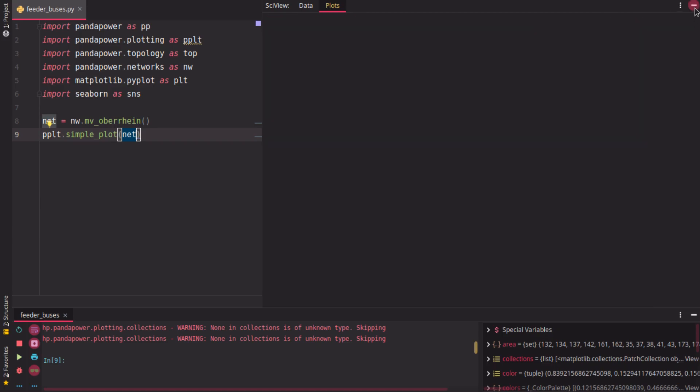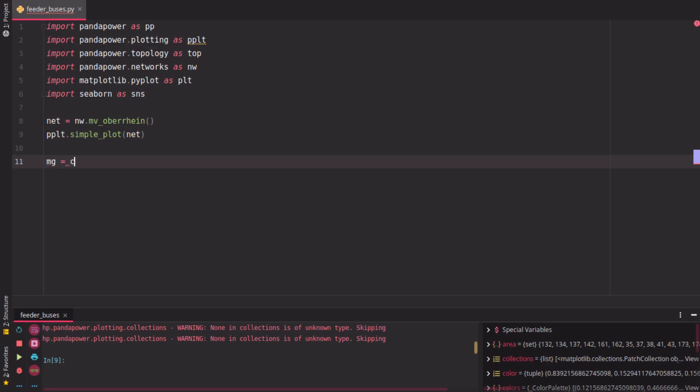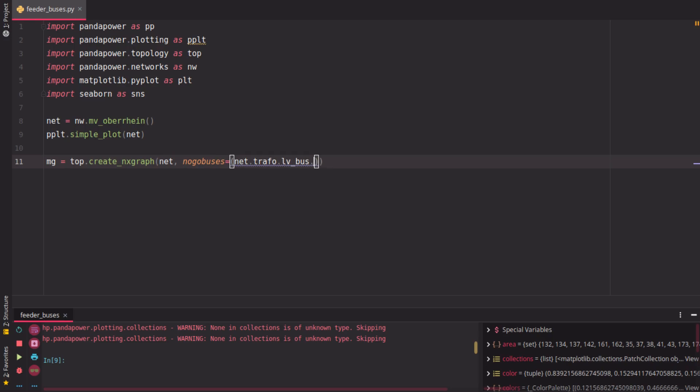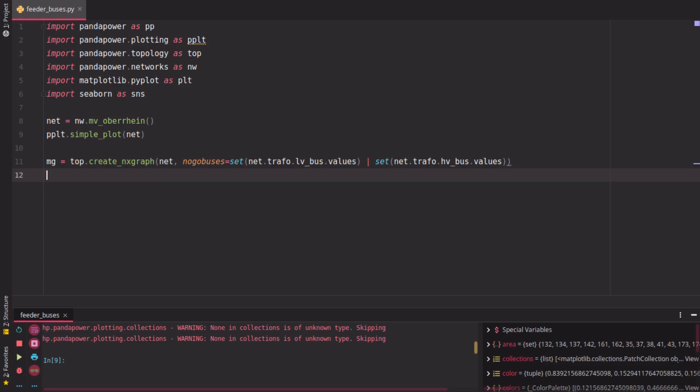This does not give you much information, and to get more information out of it, we're going to use the topology package. So first, we have to create a network x-graph for this net, and we have to specify now some no-go buses. Those no-go buses are defined by the transformer low-voltage buses or the transformer high-voltage buses. So here we create a graph which is separated, a graph for this net which is separated at each transformer bus. So now we have in this area, for example, in this multigraph four different areas because we have four transformers here.